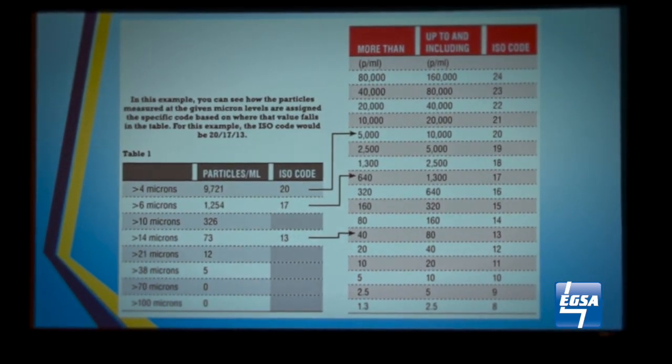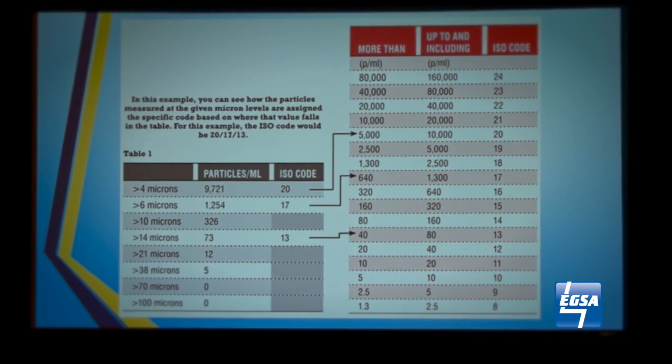With the polishing, I'll leave that to Dan. Let's talk about polishing, and Dan, why don't you also talk about the sources of contamination. Knowing what's in your tank and knowing the state is the only way you'll be able to tell your customer where they are and how you got them to the next place. ISO 4406 is testing how many particles are in the fuel. The main thing is just know what your number is and know what you need to do to change that number. Normal fuel quality — typical levels of fuel when you get it delivered — are already at an unacceptable level.